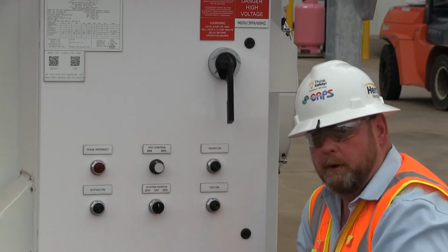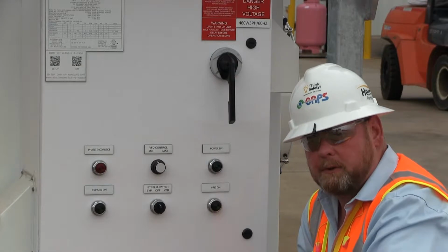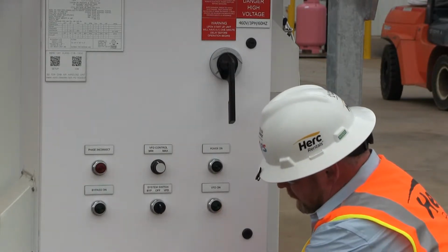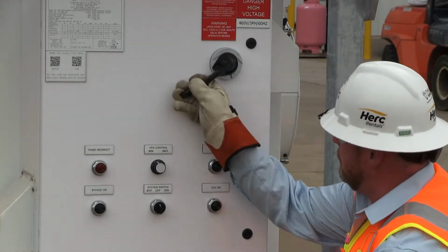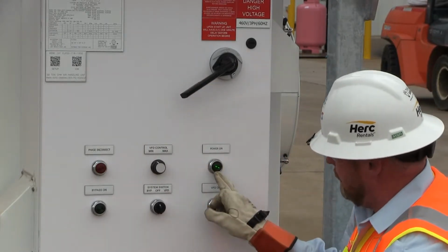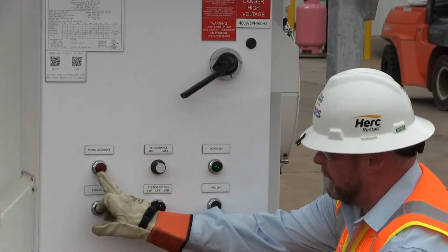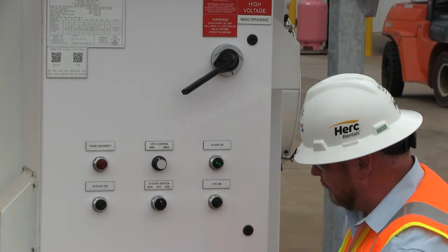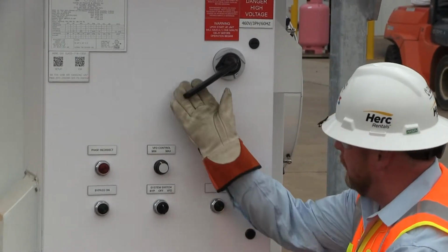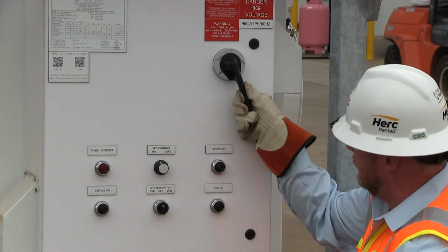Okay, we've removed our lockout tag out from our main power source. We've reversed L1 and 2 here. We're going to energize our main breaker again. This time we have a power light and our phase incorrect light is off, so we are properly phased at this point. We're going to go ahead and open our breaker back up until we're ready for our startup.